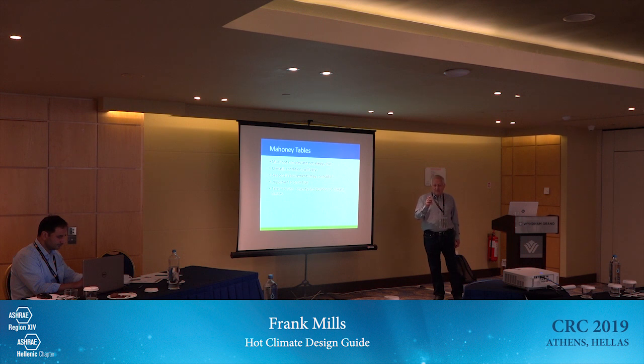Now that's his number. So other times you might say to people, what's your criteria? So someone said to me, I'll accept 1 day or 2 days, and you can do that. In the UK, in the hospitals, we say our hospitals are allowed to go over the peak temperature 80 hours. Not days, 80 hours. So it could be spread over a lot of time, or it could all occur on 2 days. But we could do an analysis and we can say what the extremes would be.